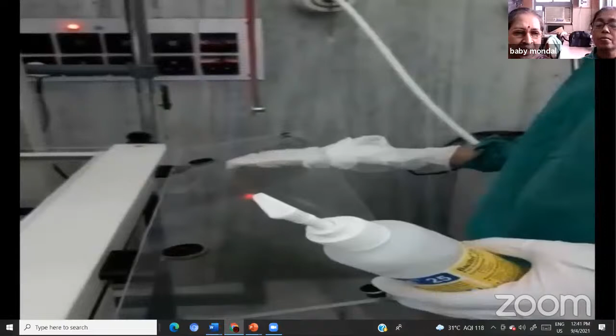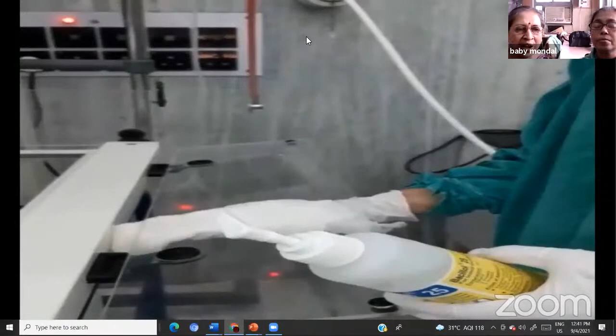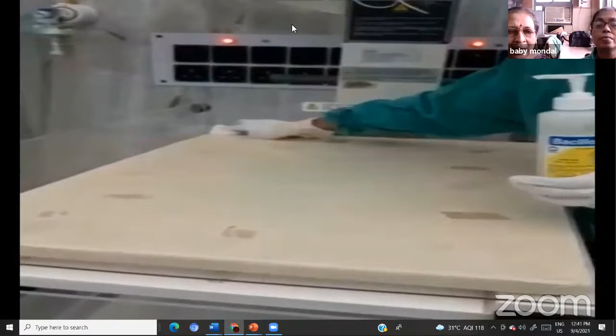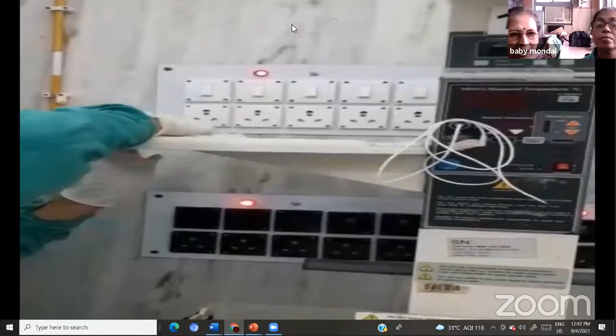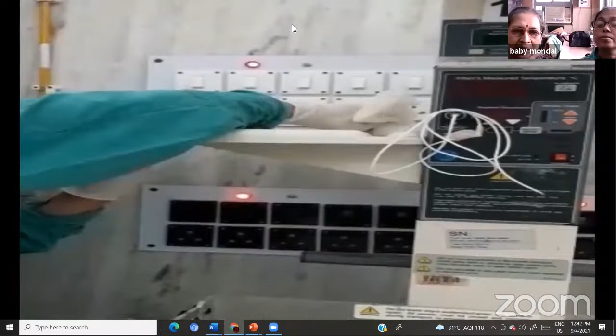But after discharge or death, or after 7 days, the body of the radiant warmer and bassinet, everything, should be washed thoroughly with soap and water. Here Bacillol 25 is used for concurrent disinfection, but for terminal disinfection we clean the whole unit with soap and water, allow it to dry, and after drying we disinfect with 2% bacillocid. For concurrent disinfection, the body of the radiant warmer and the surroundings are disinfected with 2% bacillocid solution, and the bassinet is disinfected with Bacillol. Both are shown in baby Mandal's hand.